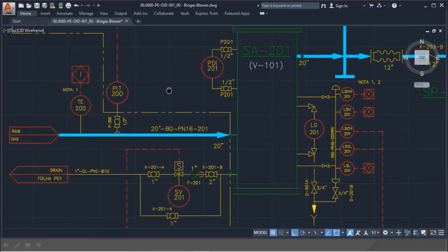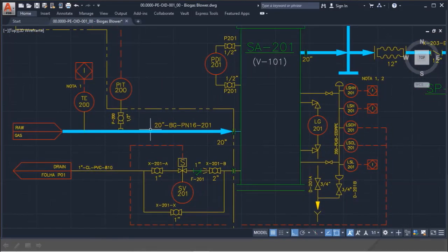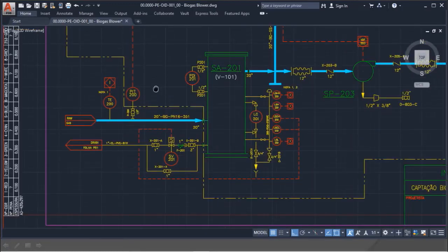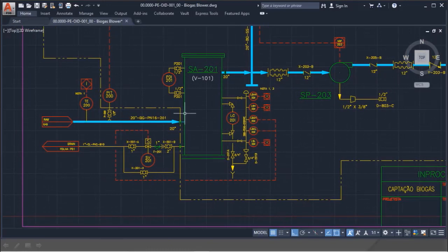And as the stream is saturated, depending on the temperature of the weather, condensate may be formed during the transportation, and we have a separator vessel with an automatic drain valve. The action of this valve is associated with the level switches that we have in the separator vessel. The lowest one is a low level switch, and we have two switches, one for low and another for high, to open and close the automatic valve.